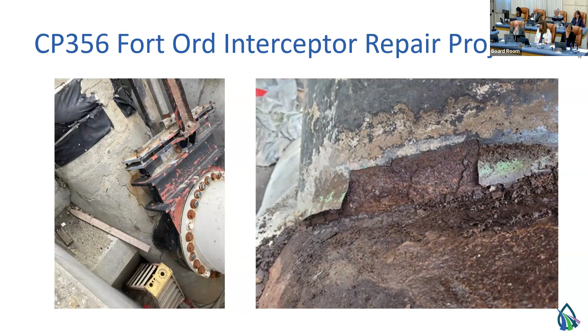The last photo was taken from inside the headworks influent junction structure, looking inside that Fort Ord interceptor. As you can see from the water line, the discharge end of the pipe is not full, so the top portion of the pipe is exposed to hydrogen sulfide gas. There's a liner bond, a glued-on plastic liner that was field-installed a few years after the plant was in operation due to damage from H2S gas exposure to the cement mortar lining. Now the liner bond is peeling back at the elbow and at the seams, exposing the pipe to H2S gas and corrosion.